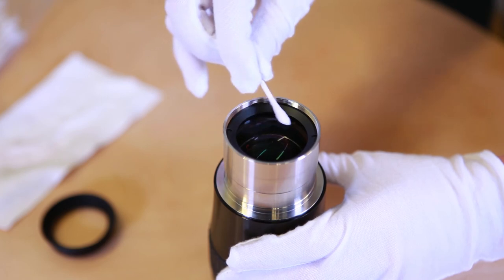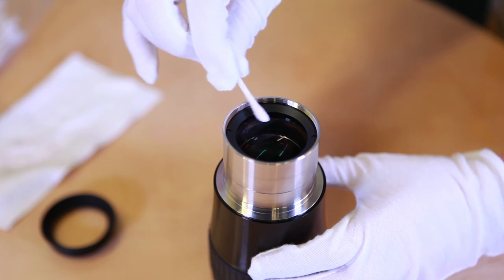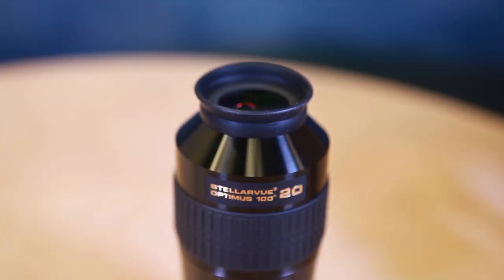First, use the bulb blower. Second, brush and bulb. And then third, clean it with the cotton swab and the lens cleaner. Once the lenses are clean, cap them and keep your eyepiece capped until you're about to use it.